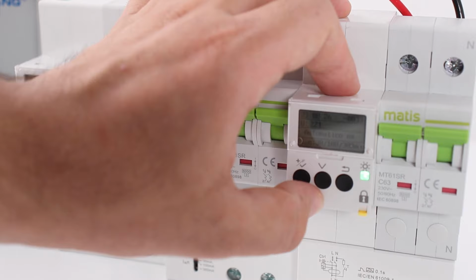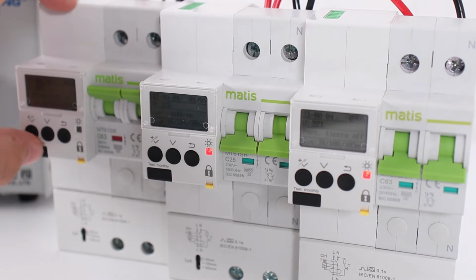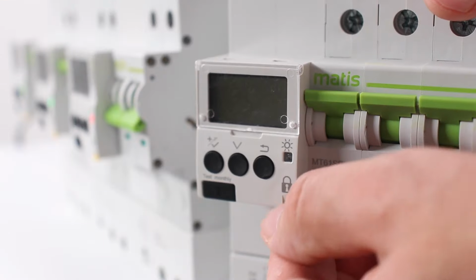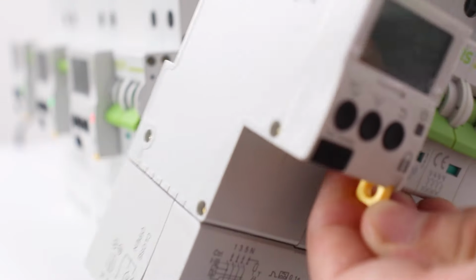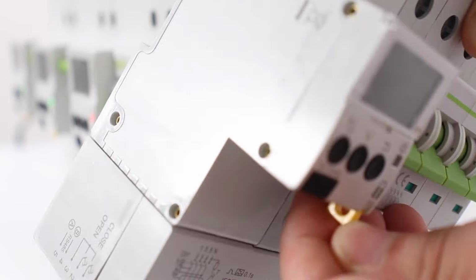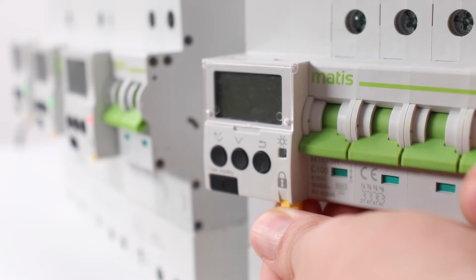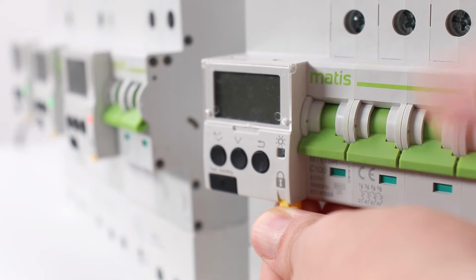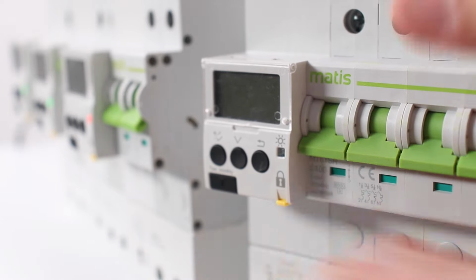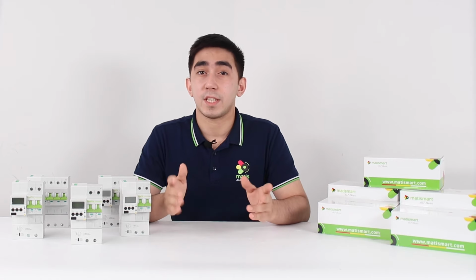Next to it is the test button to check the serviceability of the RCD. Such buttons are also available in a traditional RCD. It is also worth paying attention to this hole. Due to it, you can lock the device. If you hang a lock, then the device loses the ability to automatically turn on and remote control. This is done to ensure safety and avoid electric shock during technical repairs.